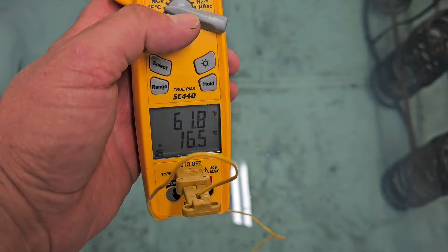Let's drop the sensor in the water and check the temperature of the water. Wow, 61 degrees. That's excellent. So from almost 100 down to 60, 40 degree drop. Let's check the temperature of the suction pipe or the gas pipe. 55 degrees. That's excellent. Now I'm going to show you how to build this.